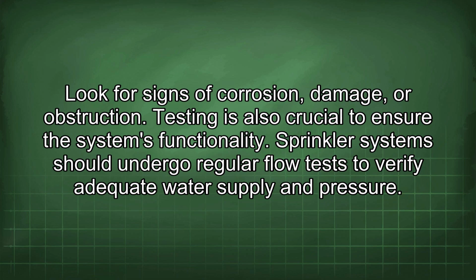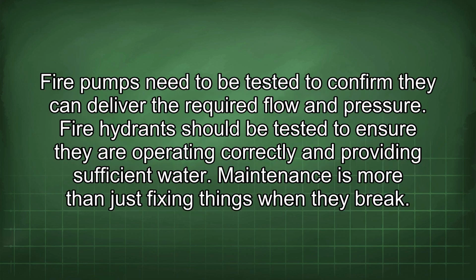Testing is also crucial to ensure the system's functionality. Sprinkler systems should undergo regular flow tests to verify adequate water supply and pressure. Fire pumps need to be tested to confirm they can deliver the required flow and pressure. Fire hydrants should be tested to ensure they are operating correctly and providing sufficient water.